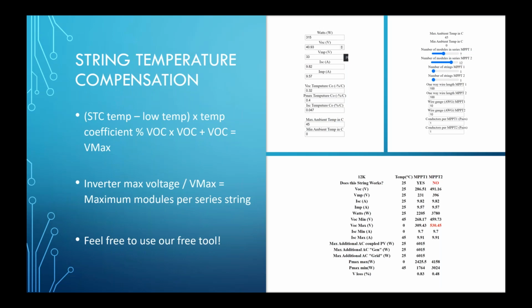Same thing with this. When it comes to stringing solar panels to the Sol-Ark inverter, again, there's 2 ways to connect. You can AC couple or DC couple. If you AC couple, you're literally bringing in AC power from an inverter that has a solar system already. Might be a Fronius, might be Enphase microinverters, could be an SMA, might be a SolarEdge. We AC couple to those systems and those inverters all the time. So that's one way to do it.